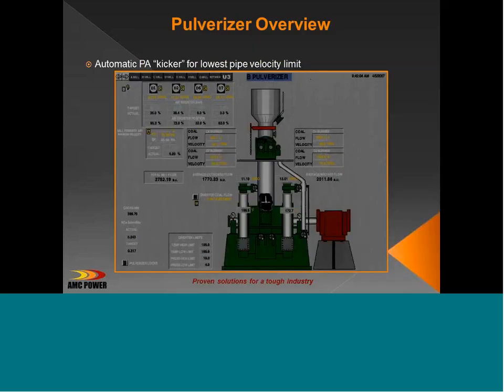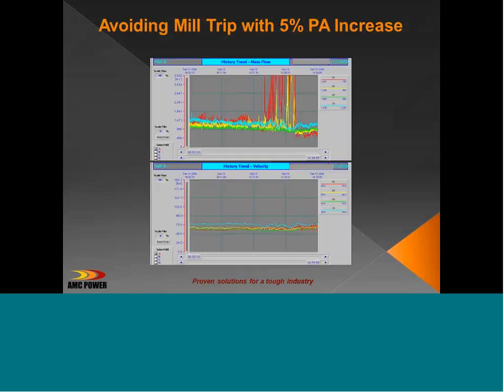In the event that this happens, up here, whichever mill happened to get this PA kicker will flash, letting the operator know, I've got a primary kicker on a mill. The operator can click on that mill button, and then it will take him back to the data, so we can see exactly what caused the control system to put in a primary air kicker.